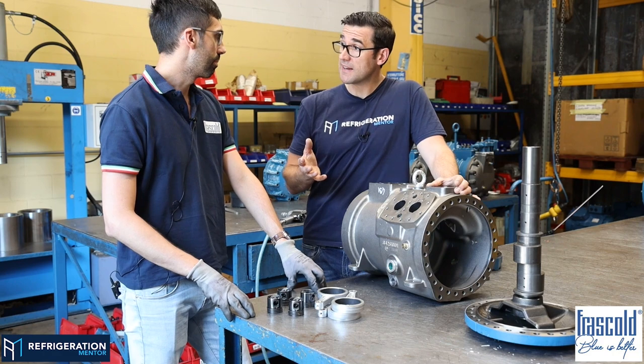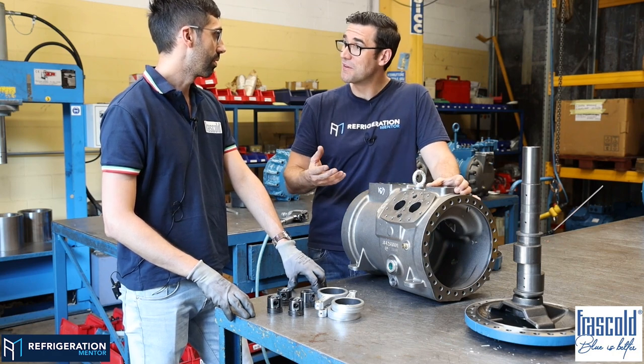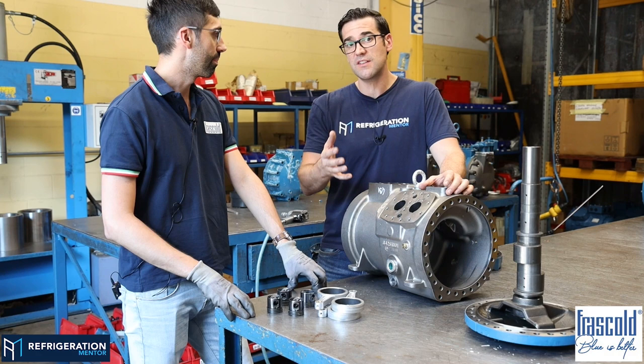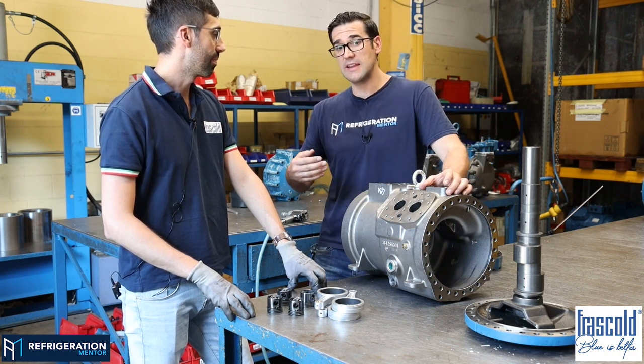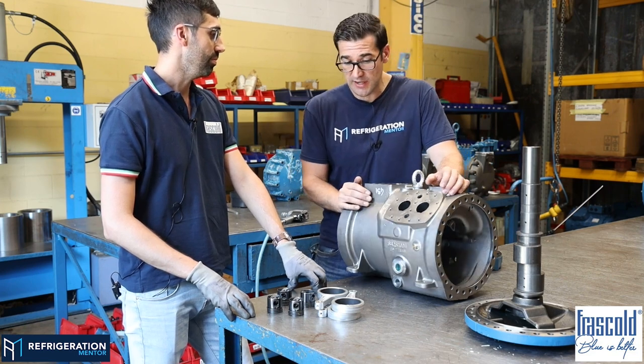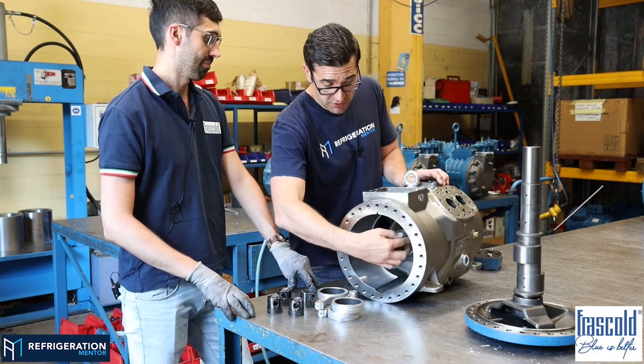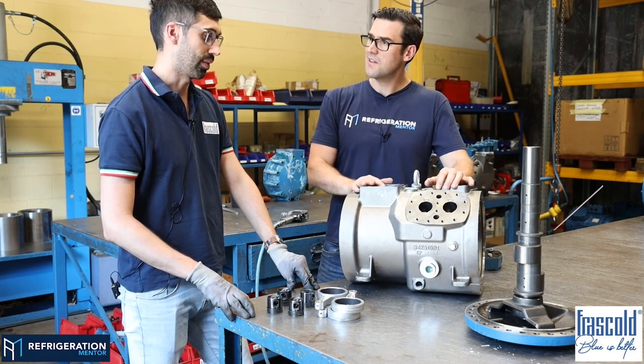You would call that flood back now. So the compressor at this point is running, because this is not the way I talk about flood back. So this is good, now this compressor is running. And just say your metering device, your TX valve, fails open. You get a piece of copper jammed in it and all of a sudden you're satisfied, but you've got a ton of liquid coming down that suction line. This would be another way to get a liquid hammer, a slug, where, like you just explained, it goes through here, the liquid comes up here and then we have the smash, yes.